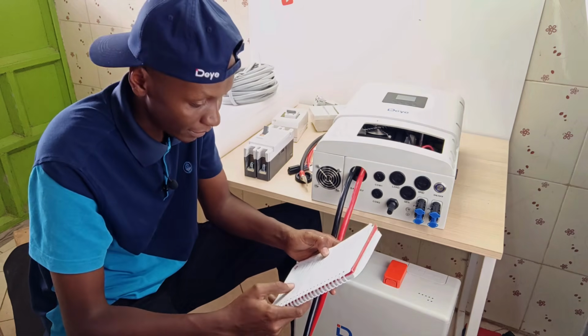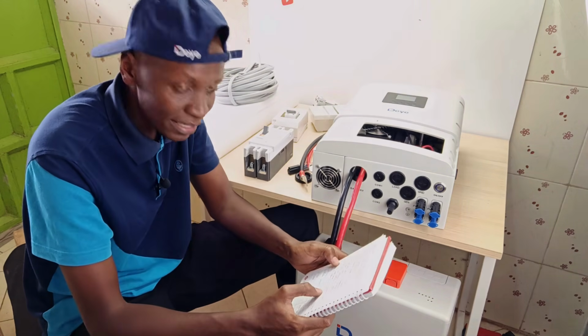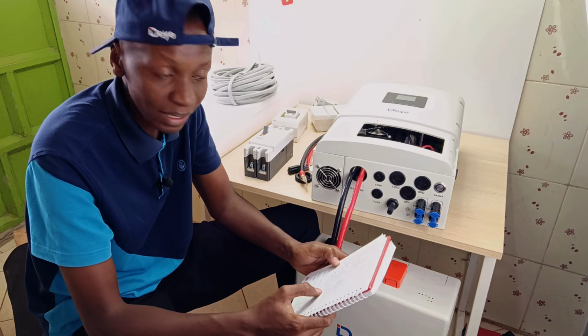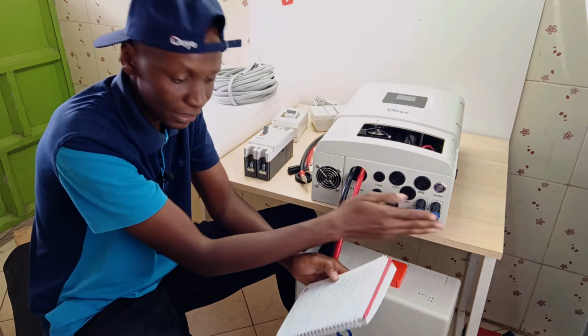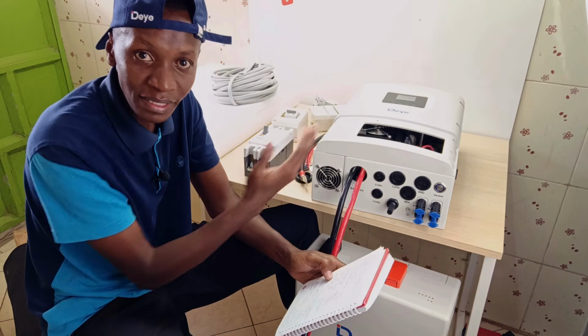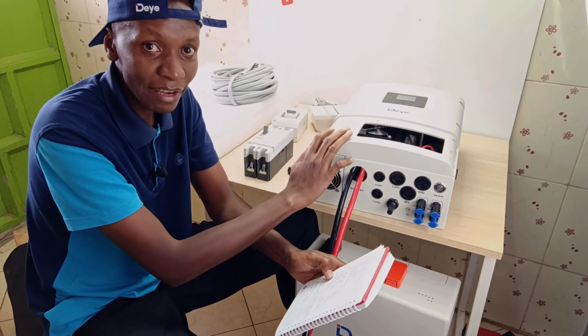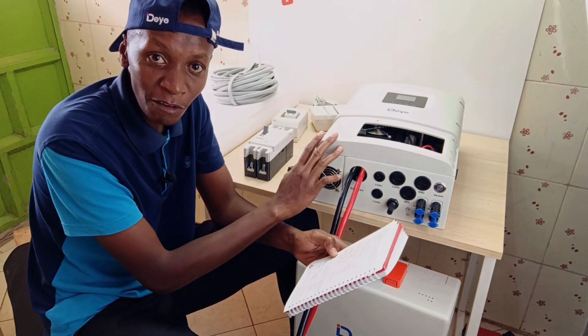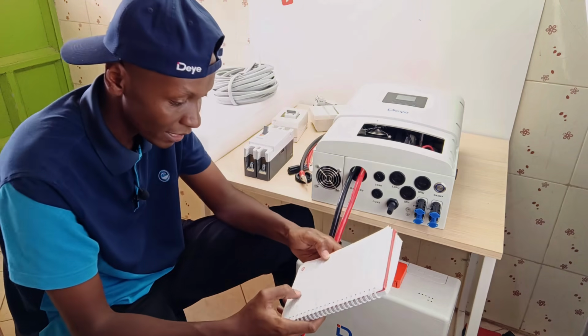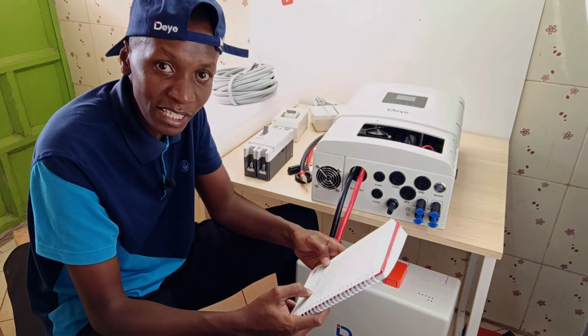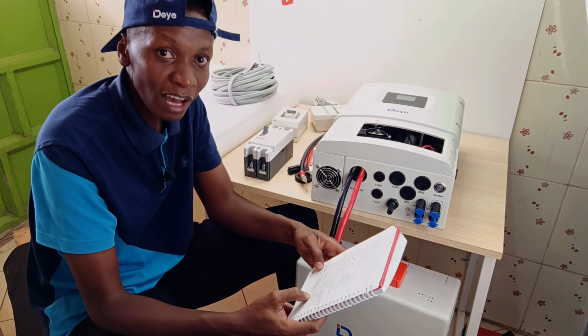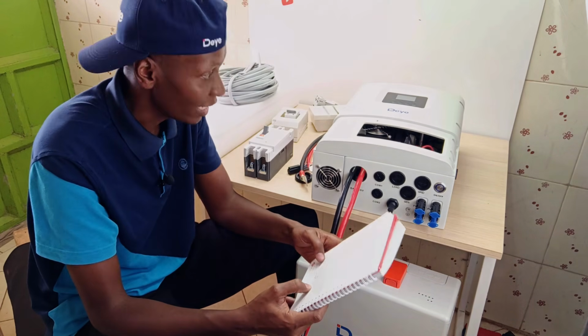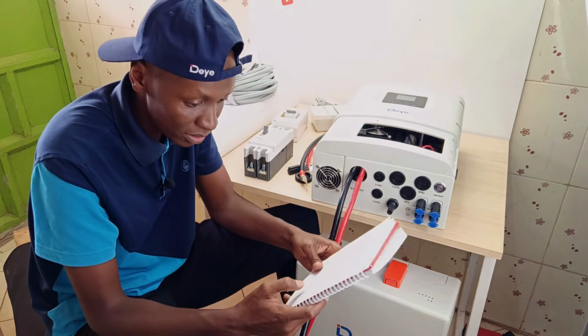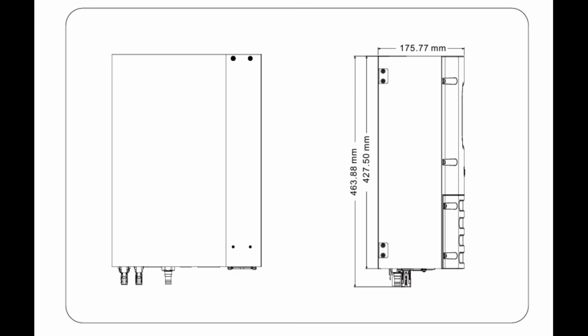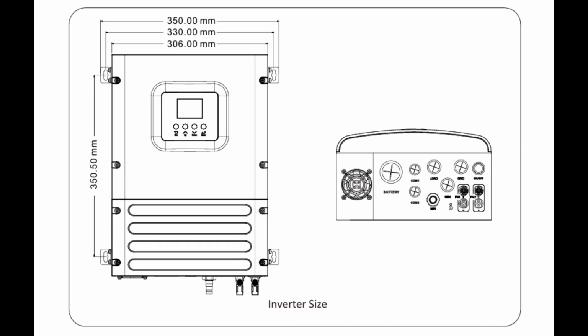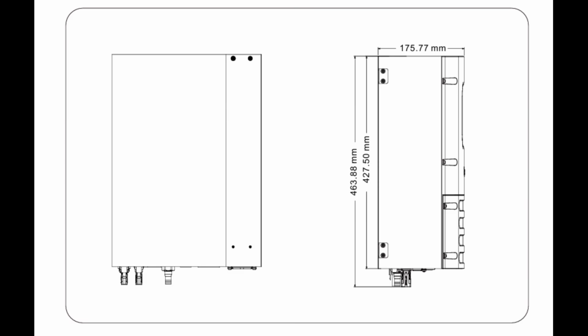Take note of that. The maximum solar input current is 18 amperes plus 18 amperes. Like I said, twin MPPT. And the rated output voltage, this is an EU model, it's 230 volts. The efficiency of this inverter is 97.6%. It weighs around 12.65 kilograms and comes with a 5-year warranty. The dimensions, which are the maximum dimensions, are 463.8 millimeters by 350 millimeters by 175.77 millimeters.